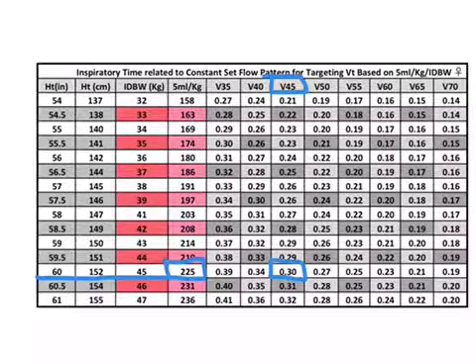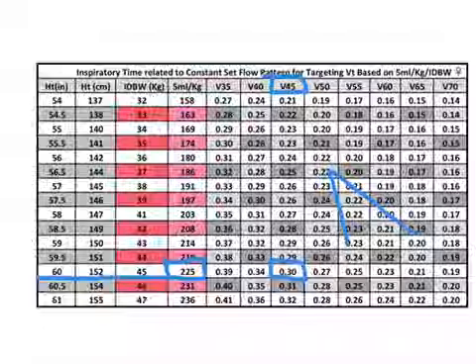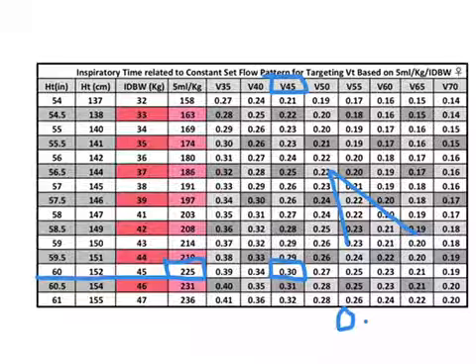Or if you're using a fully decelerating flow waveform pattern in your ventilator, this would double. So my inspiratory time would be 0.6.